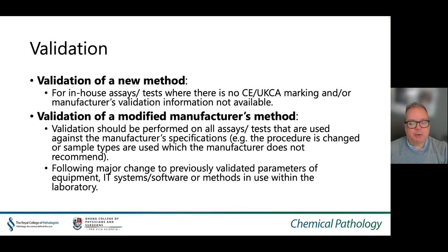In summary, a validation would take place when you are validating a new method — for example, in-house assays or tests where there is no appropriate international marking standard available, or where method validation information is not available. You could also validate a modified manufacturer's method, and validation should be performed on all assays used against the manufacturer's specification, for example where the procedure is changed or the sample types used are not what the manufacturer recommends.